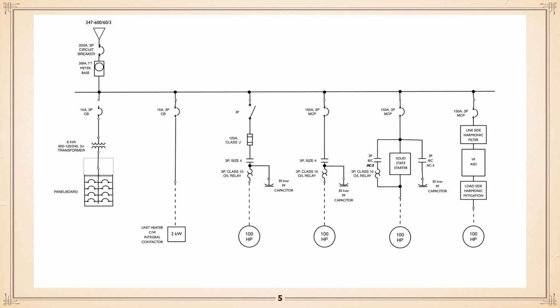With that arrangement, it does not have to be a combination load center, because if you kill that 15 amp breaker, obviously you kill the transformer, and by doing so, the panel board is no longer energized and poses no threat. The next one over is showing for a heater, again, just a 15 amp breaker, feeding onto the heater, which has its own overload and everything else built in. The next one is a fused over current arrangement with the disconnect. The class J fuse. The J breaker is the dual element, or anyway, what's the other expression for dual element?